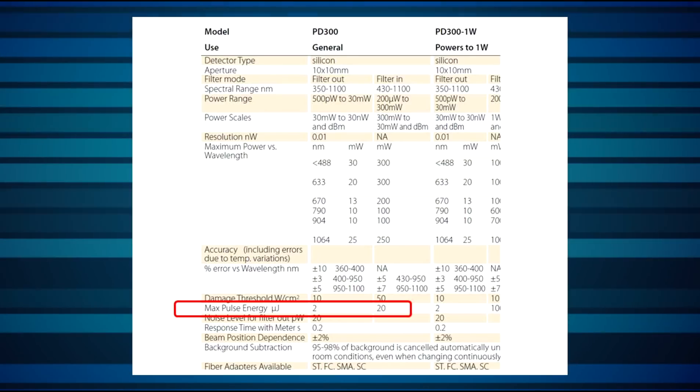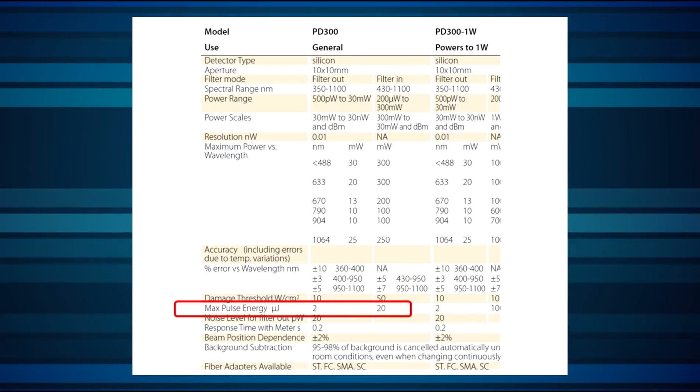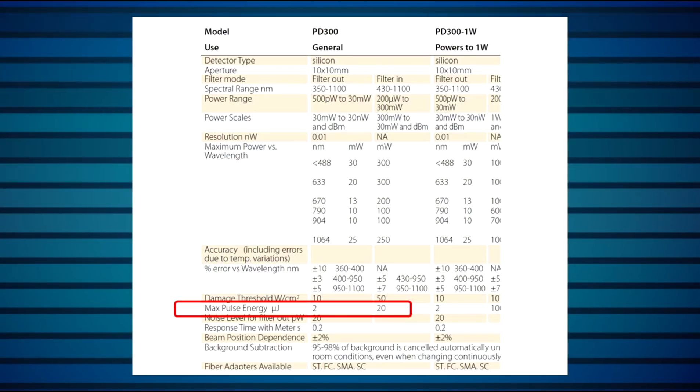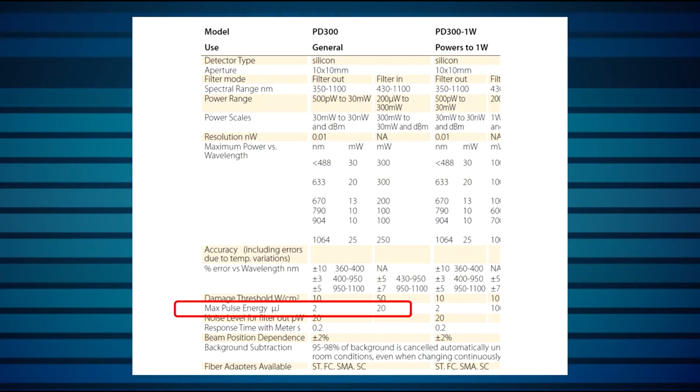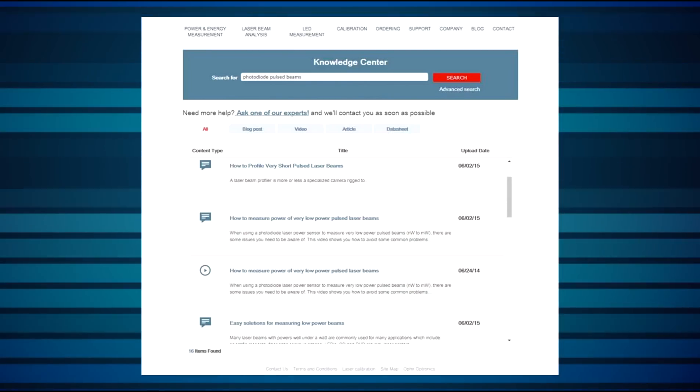If you're measuring power of a pulsed beam with a photodiode sensor, there are two issues to consider. First, the maximum pulse energy is listed in the sensor spec sheet. This is important even though we're not actually measuring energy, since too high pulse energy can cause momentary saturation of the detector, which can lead to inaccurate measurements. Second, for measuring average power of pulsed beams having pulse rates less than about 100 Hz, we generally don't recommend using photodiode sensors if possible. This is because of a number of effects related to the fast physical response time of photodiode sensors, discussed in detail in tutorials and videos on our website.